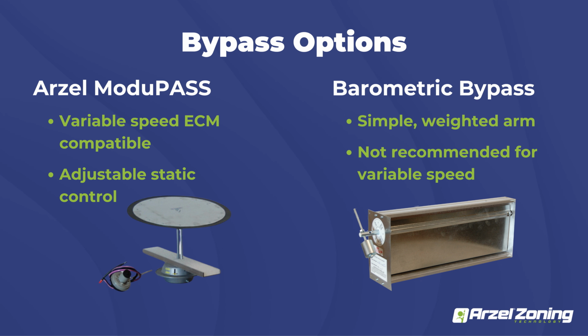And the reason being is you can get what they call hunting, where the motor starts chasing your bypass open and closed. You'll have a customer say, hey, since I've had this installed, my motor's ramping up, ramping down, ramping up, ramping down on a call for conditioning. And that's typically what's happening, is that as that bypass opens, that motor starts speeding up to make up that difference, and then your bypass starts in a loop of just chasing each other.